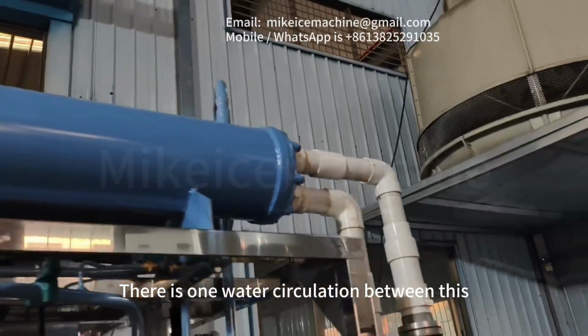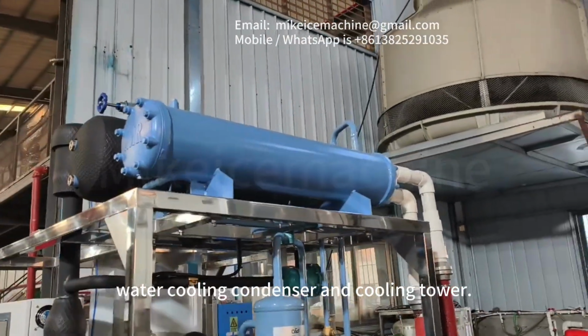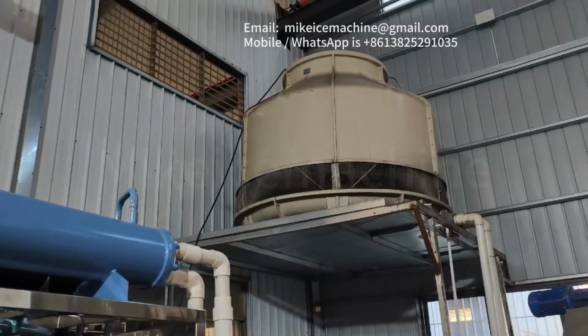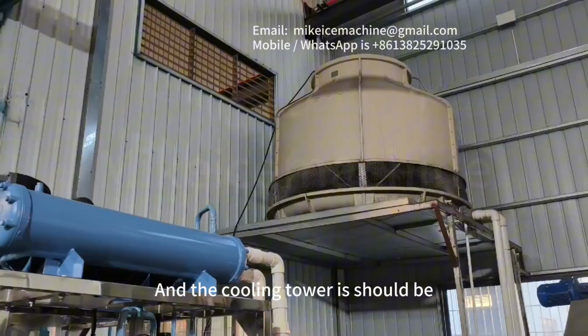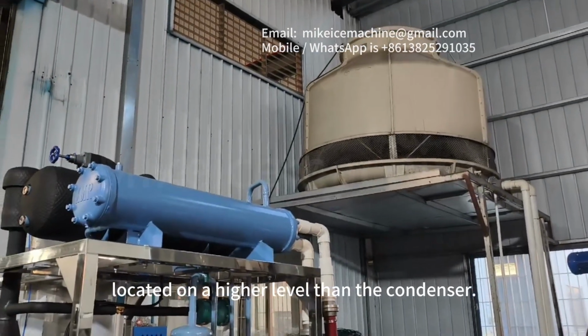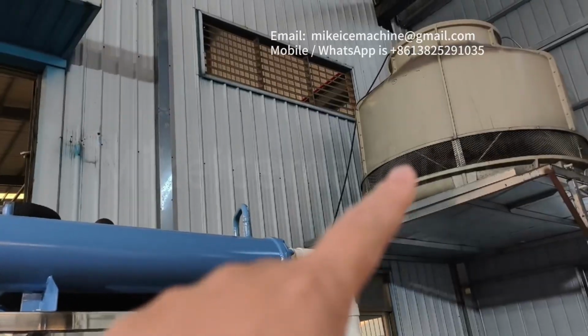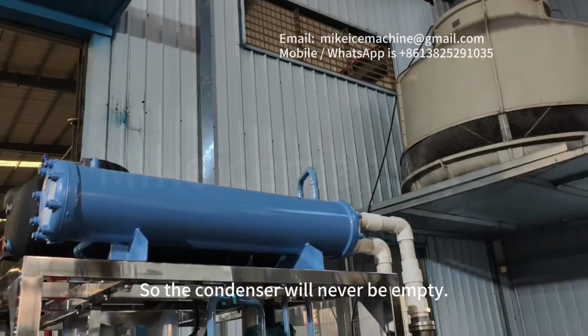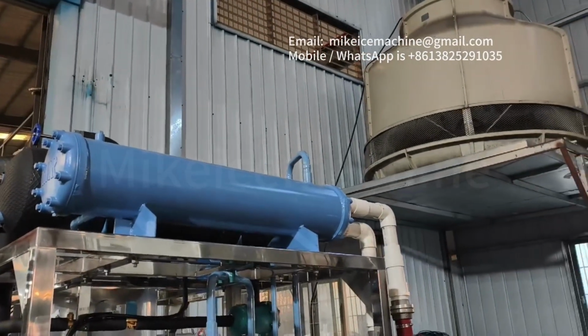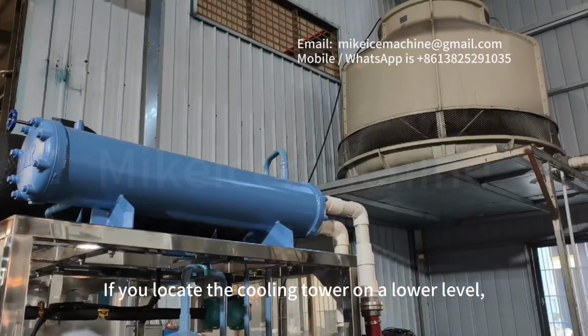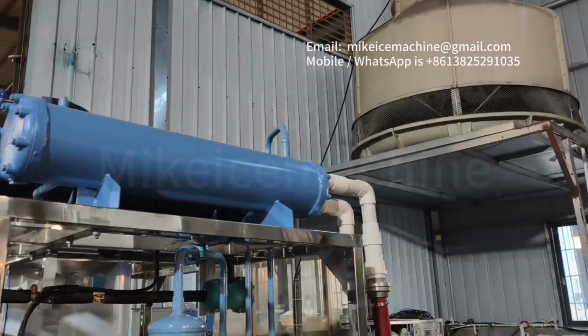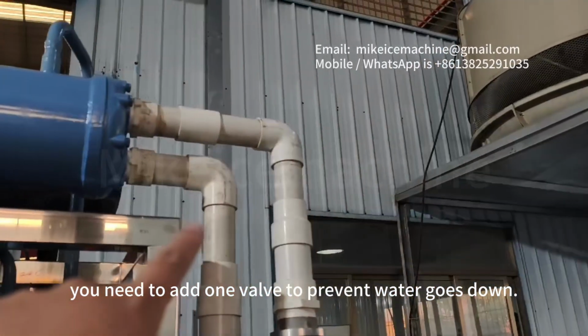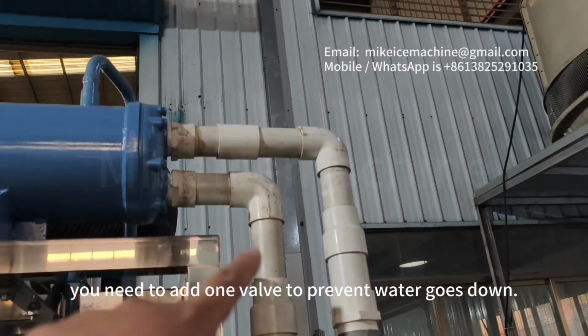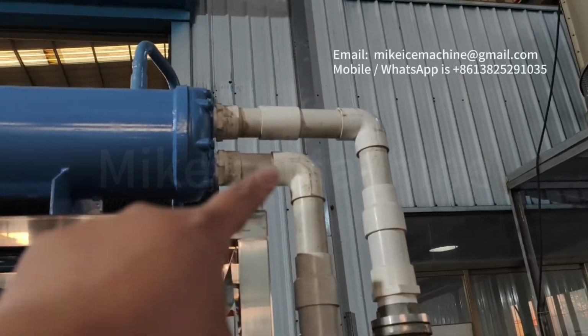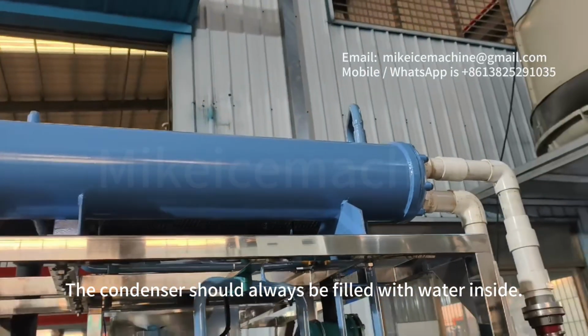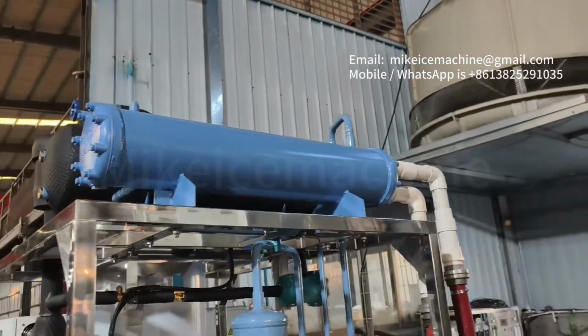There is one water circulation between this water cooling condenser and the cooling tower. The cooling tower should be located on a higher level than the condenser, so the condenser will never be empty. If you locate the cooling tower on a lower level, you need to add one valve to prevent water from going down. The condenser should always be filled with water inside.